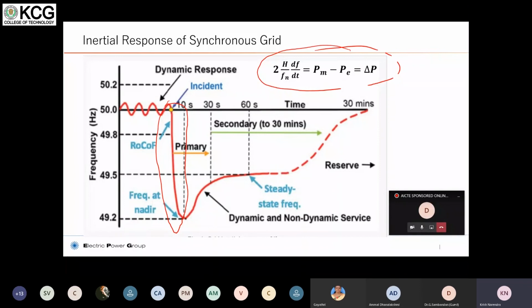The inertial time frame is the time frame where the only support available to the grid is the rotational kinetic energy stored in the system, which is given back to arrest the frequency drop. The lowest frequency it reaches depends on the synchronously available inertial support in the system. A good inertial support system can make sure that this drop happens at a very small value and doesn't allow you to drop too much, because dropping too much has a lot of consequences, which we will discuss.